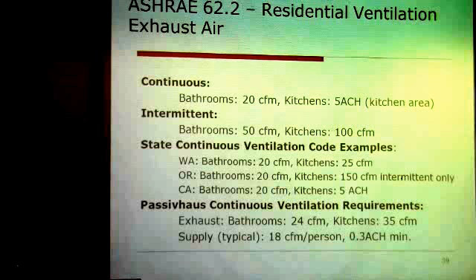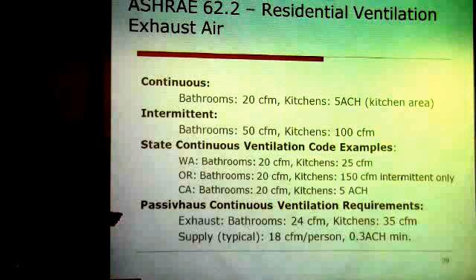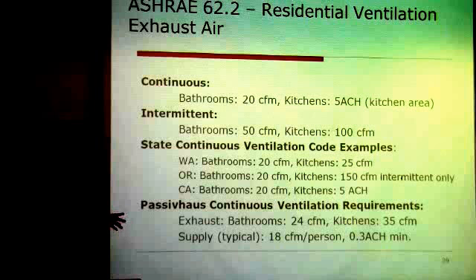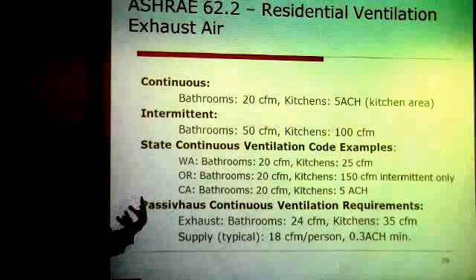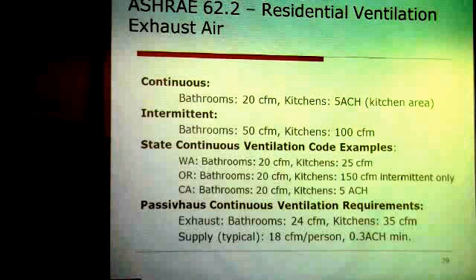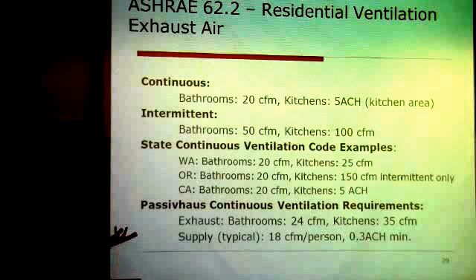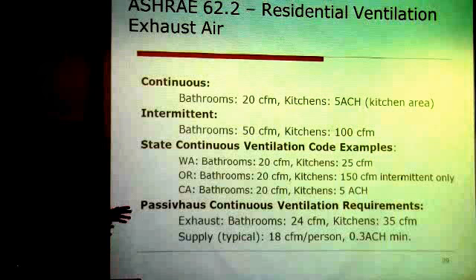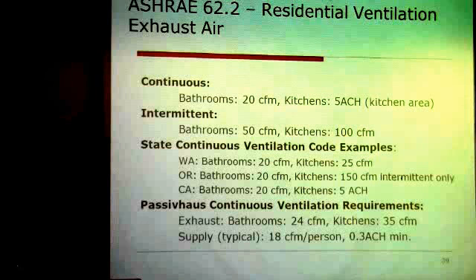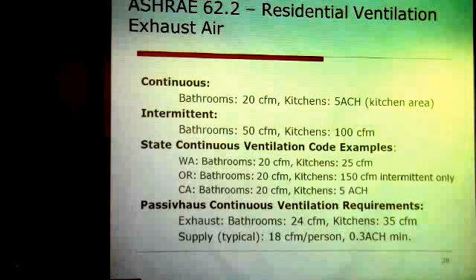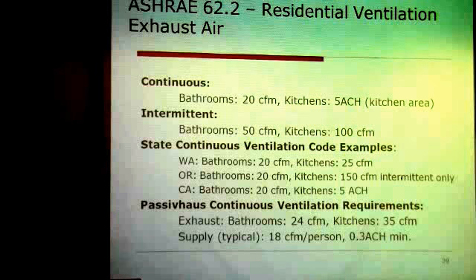For 4 people, that'd be just less than, what's the number on that? 72? Did I do that right? 72. And then the other one's about 83 or so. So in that case, the exhaust would dictate. You design the exhaust for continuous of around 83, 85 CFM, and then you meet passive house. And then you also check to see if that's around 0.3 ACH, and that's kind of your design.